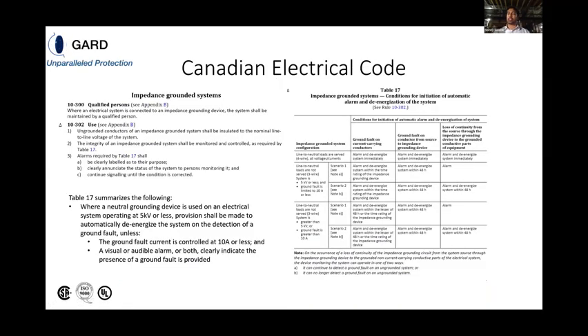Now, in the Canadian Electrical Code back in 2015, we really didn't have a reference for impedance grounded systems, but due to a lot of requests from consultants that are speccing out impedance grounded systems, they decided to implement some clauses in Section 10 of grounding and bonding. Further to this, in 2021, they gave us a really nice table called Table 17.